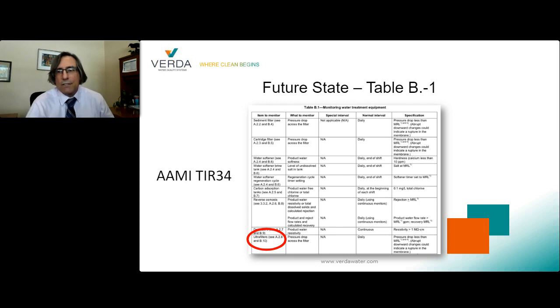A good check to see if you are out of compliance is to ask the question, is someone checking on the treatment equipment every day? This is usually a small room located near the department. If someone from the department or another department or the equipment service provider is not going into the room daily, checking equipment and writing down values, you are likely not complying with the AAMI guidelines.